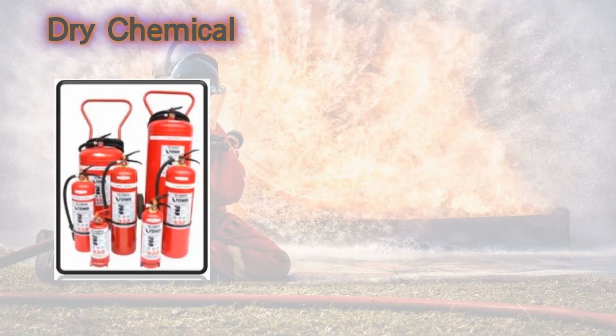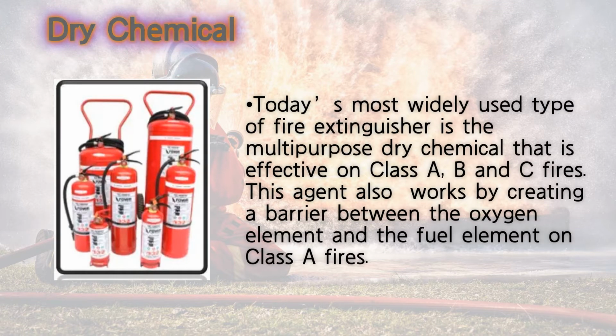Dry chemical. Today's most widely used type of fire extinguisher is the multi-purpose dry chemical that is effective on Class A, B and C fires. This agent also works by creating a barrier between the oxygen element and the fuel element on Class A fires.